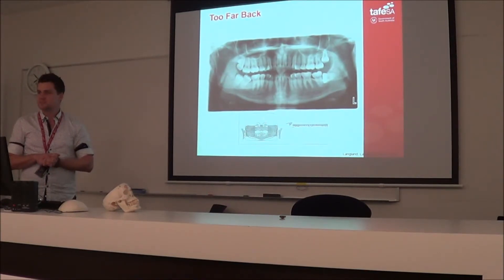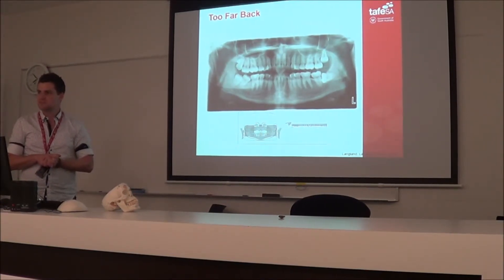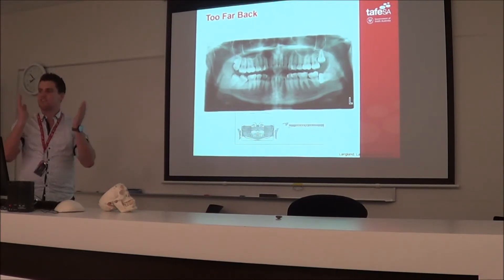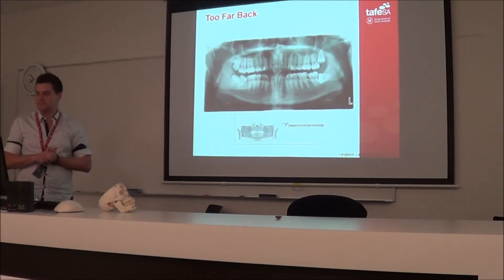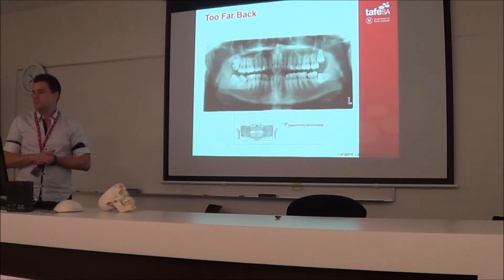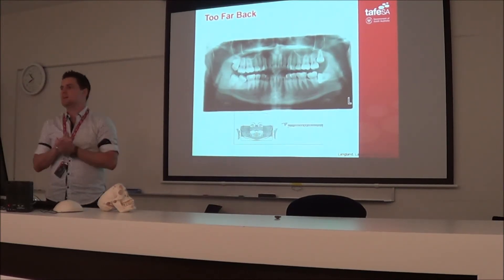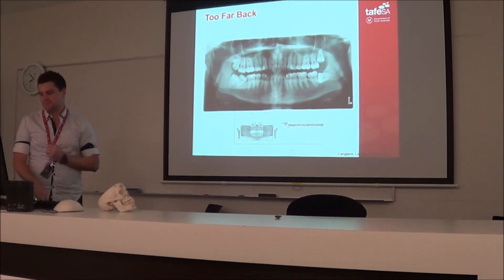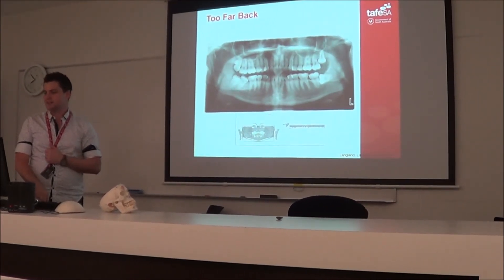What does that mean? You can't see the condyles or the TMJ joint on the x-ray — it's actually gone off the edge of the film because it's too wide. The third factor you usually see is that the film is generally a lot lighter, because when we increase the object-film distance, we usually get a whitened image as well. X-rays have to travel further towards the sensor after penetrating the object, so the image appears lighter.